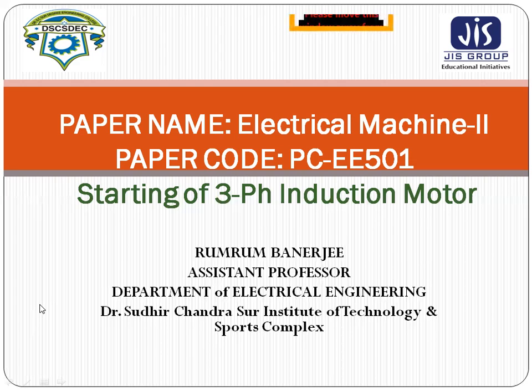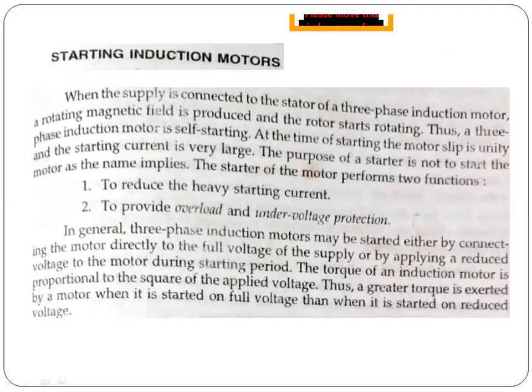So now we will start with today's topic, that is starting of three-phase induction motor. When the supply is connected to the stator of a three-phase induction motor, a rotating magnetic field is produced and the rotor starts rotating. Thus, a three-phase induction motor is self-starting. At the time of starting, the motor slip is unity and the starting current is very large. The purpose of a starter is not to start the motor, as the name implies. The starter of the motor performs basically two functions. One, to reduce the heavy starting current, and secondly, to provide overload and underload protection.